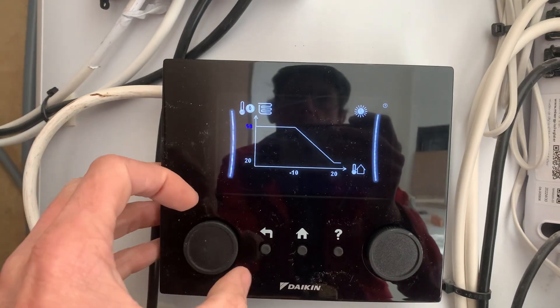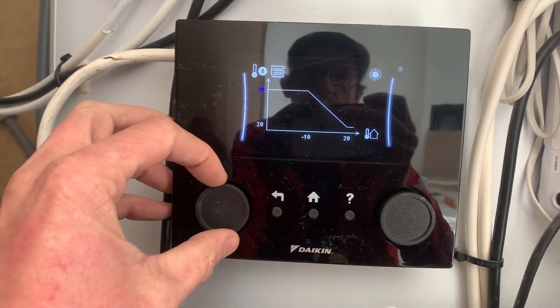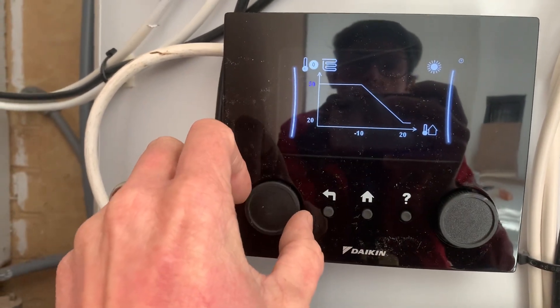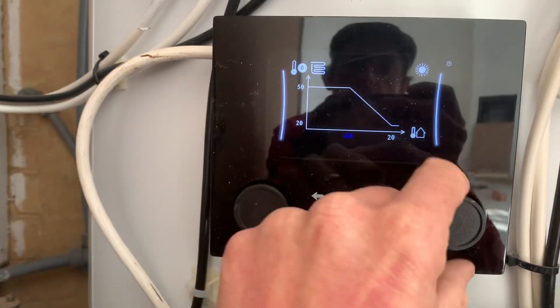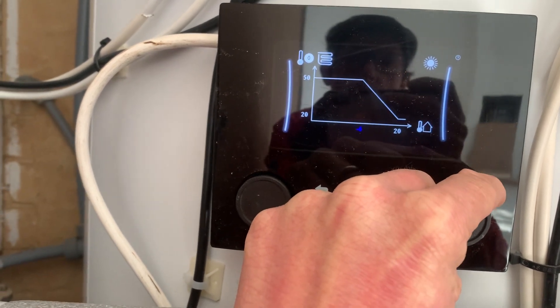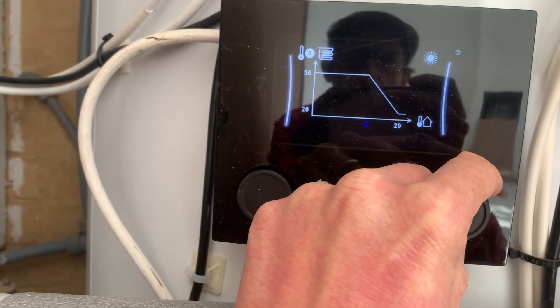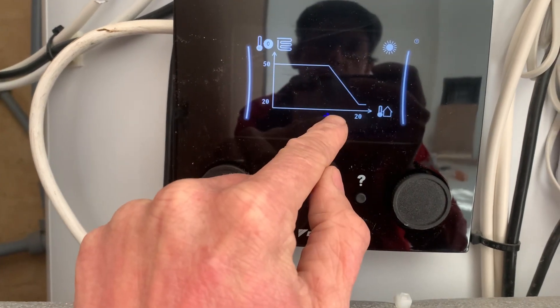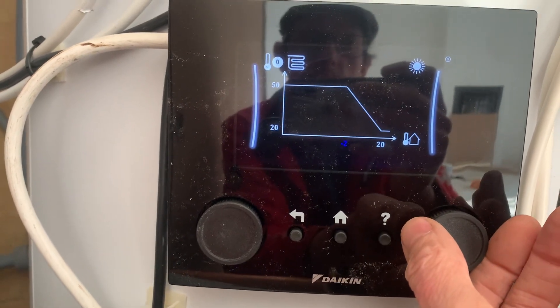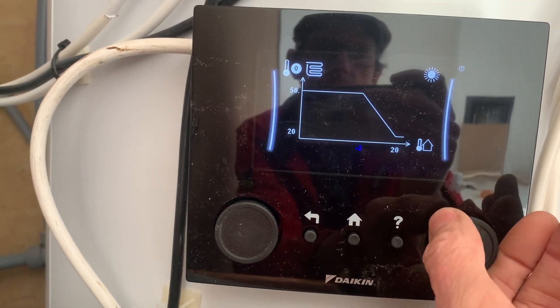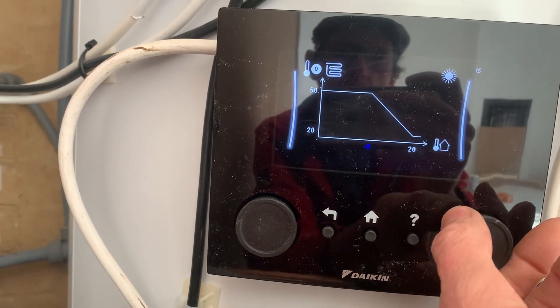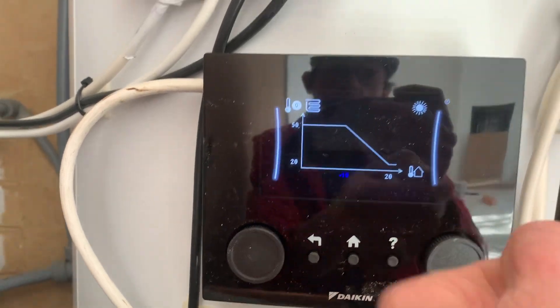If you find that the house isn't getting to around 20 degrees, you can alter this — maybe try minus seven. But ultimately the system is designed at minus two at 50 degrees. Because you're running weather compensation you generally don't need it to be that warm, so to make the system more efficient we can run it cooler since it's on for longer — or on all the time. We'll go for minus 10 and then see how you get on.